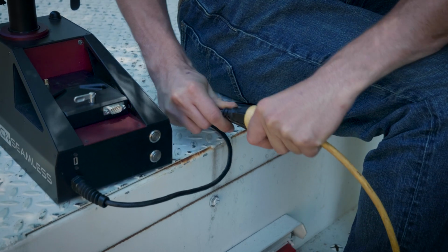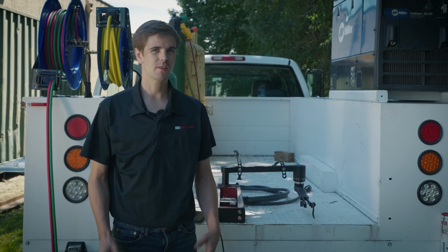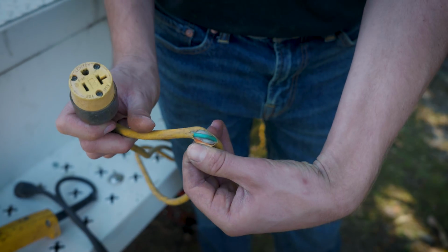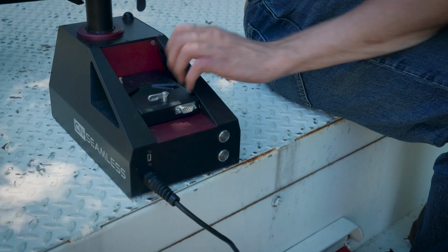So the first thing is make sure you have good power. To check this, plug in the machine and see if the magnet turns on. If the magnet doesn't turn on, pretty much the only thing that would cause that is if you have bad power. It runs directly from the power supply and doesn't interact with the computer at all.